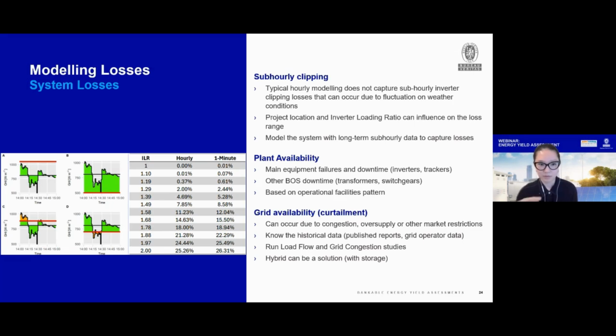The table is from a resource where different inverter loading ratios were measured, comparing hourly modeling versus 1-minute actual real data. As you increase your inverter loading ratio, it increases the difference between hourly and 1-minute modeling, up until it gets to a point where the inverter loading ratio is so big that it doesn't matter anymore.